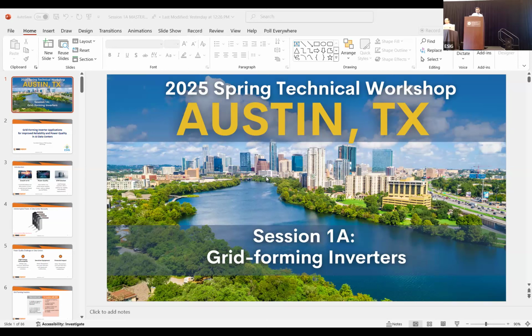So with the Tesla Megapacks, both transient and steady state response management is possible. Here in this slide, you can see step by step what happens within the Tesla grid forming once a grid event like loss of a big generator happens. When we lose, let's say, a big generation plant, the frequency drops suddenly and sharply, and at this point, the inverter's inertia and droop push the power beyond the operational limit of the power temporarily for a few seconds, and then the reference values at the machine level are refreshed in order to make the reference value equal to the real actual frequency of the grid.